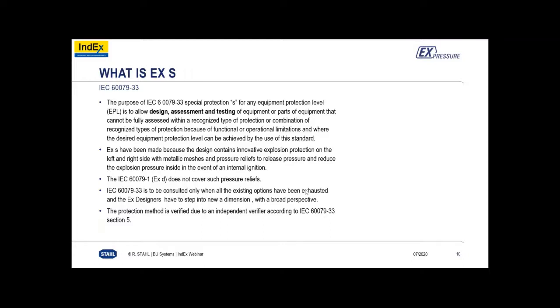It was a long period of development of the enclosure, and we released ExPressure 2 years ago on the market. It's covered by the IECEx certification and also ATEX. So it has been approved and it is well trusted. Both these standards, which cover it, 60079-1 and -33, are approved by EN and IEC. Yes, the method of EXS is verified by 2 independent verifiers, as it also says in the standard, and they are members of the test laboratory and the certification body at PTB and DEKRA. You can find it also in the certificate.